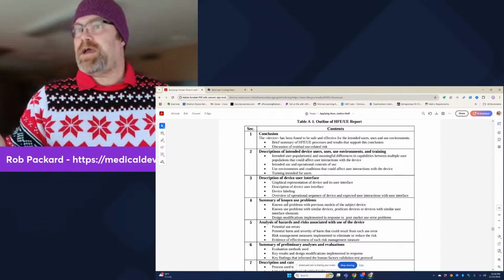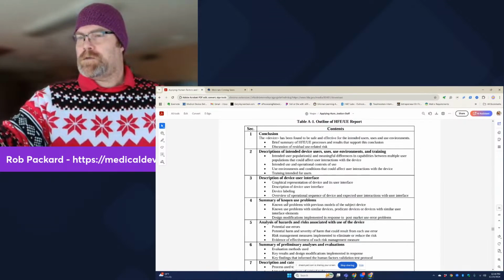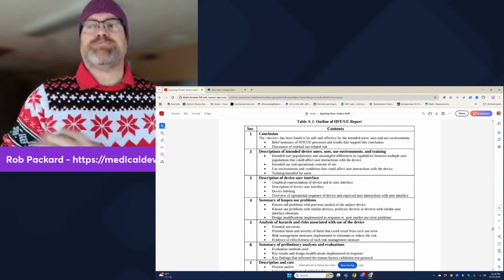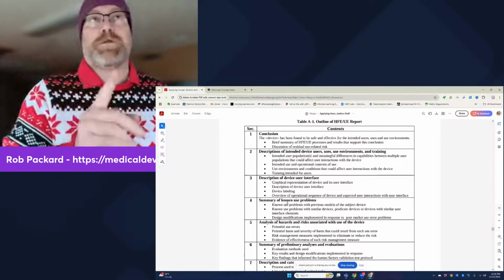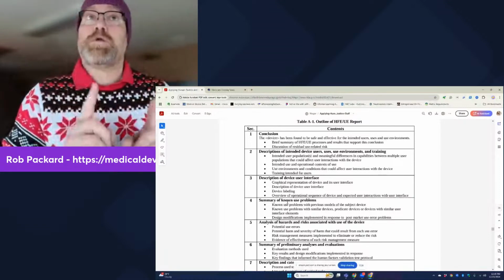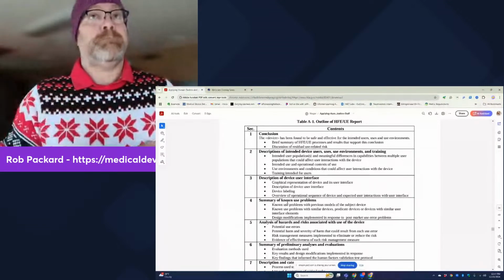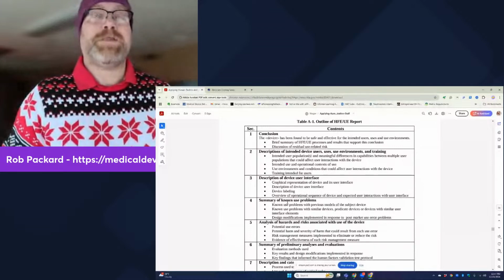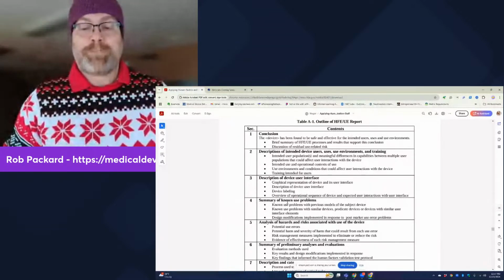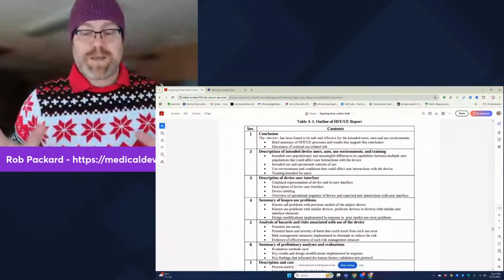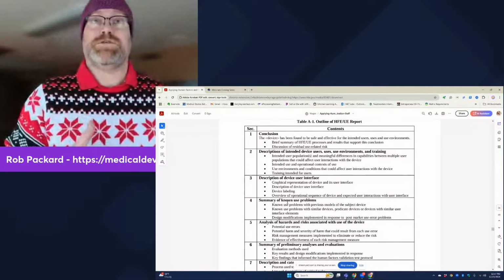So they have, where is it? Section 4, last bullet, design modifications implemented in response to post-market use error problems. So this could be your post-market for your last version of your device. It could be formative testing, or it could be a competitor's product, or all 3. So that was trap number 3. You don't want to fall into that trap and not have the information that you need. A lot of people struggle with that one because they didn't do their homework and didn't read ahead.